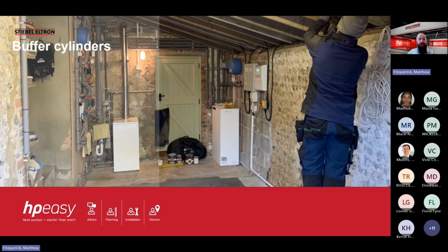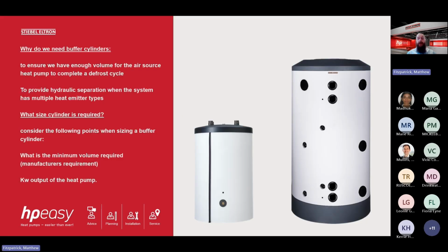Buffer cylinders. So compared to the fossil fuel heating systems, they do not normally require a buffer cylinder unless it's a large commercial project, or there's multiple heat sources going into the heating system. So with renewable heating systems, a buffer cylinder can be required or may be required when you need to ensure you have sufficient volume for defrost cycles. I think I've mentioned this in previous segments, but I'll just recap.